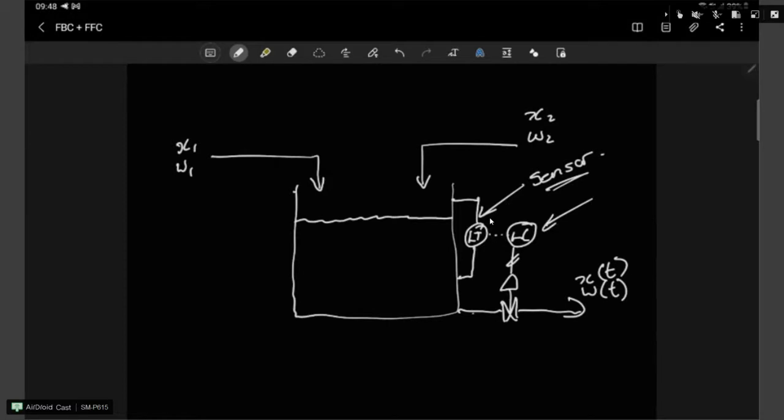Then the controller is obviously some form of a device that can compare the input value of a set point to our measuring input value and say, okay, well, it's below or above. And depending on the settings that you implement on that controller, it will take some form of a control action. So in the event of a fridge or freezer, typically your ambient conditions are at a higher temperature, so your control action is inverse. It's the other way around. So we refer to reverse acting or direct acting. You don't need to worry about that just now, but in the event of a heating system, obviously the output must go on if the temperature is below. In a cooling system, the output obviously goes off when the temperature is below the set point.